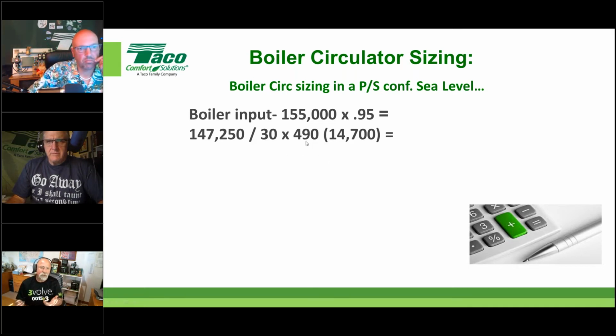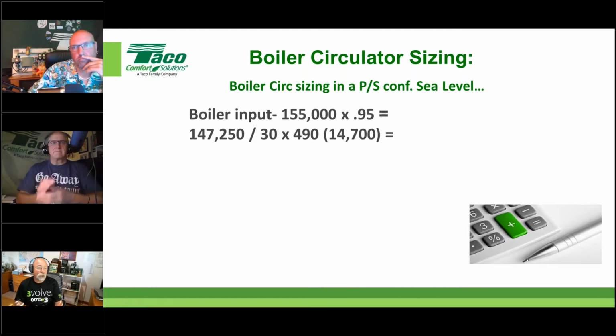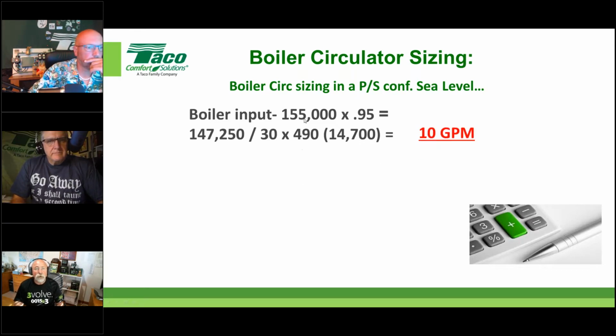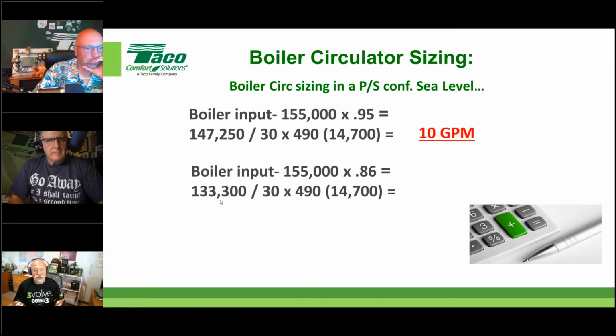So when water's elevated in temperature, it's less dense and it can't carry as much energy. So we use a multiplier change there for our constant. So it's 14,700 as a result of this. That tells me I only need 10 gallons a minute to do a 155,000 BTU boiler. Most people would, at the minimum, put a 15 gallon a minute pump in there, just shooting from the hip. Okay, here's the same boiler at a lower efficiency. So again, 0.86 gives me 133.3, 30 degree delta, 490 is my constant. That just says I've got 9 gallons a minute.